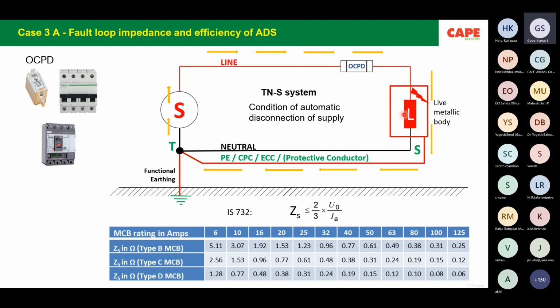Maybe after a few years, instead of checking the earth pit resistance, everybody will start checking the fault loop impedance. Please note that fault loop impedance is not the only test required. There are several, but probably I would say one of the important. In IS 732, Part 1, Section 18, this table is included. This table tells you the maximum allowed fault loop impedance depending upon the type of MCB. For example, for a 63 amps type C MCB, the impedance of the circuit shall be less than 0.24 ohm.